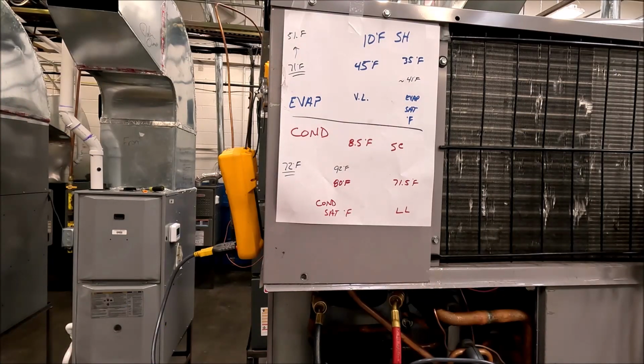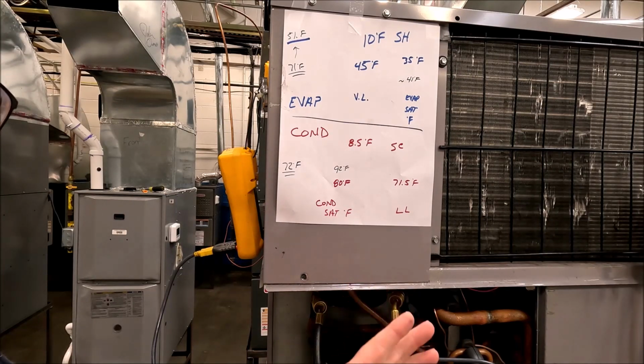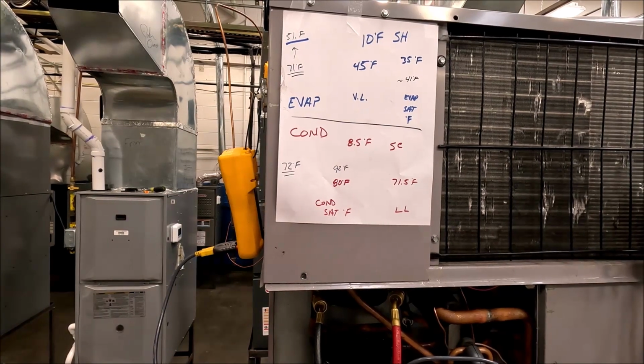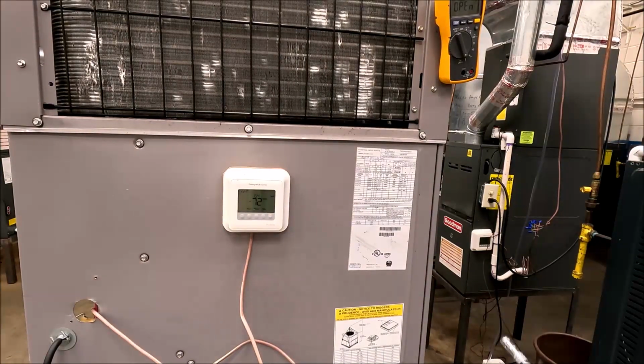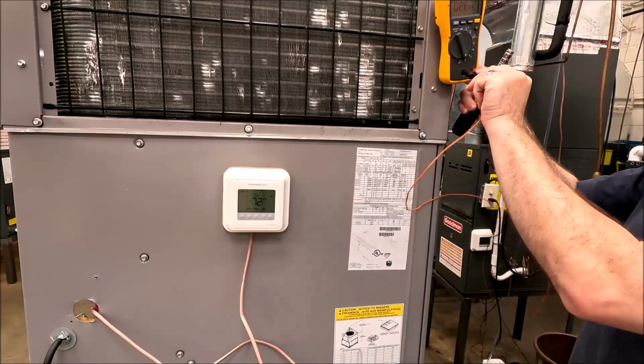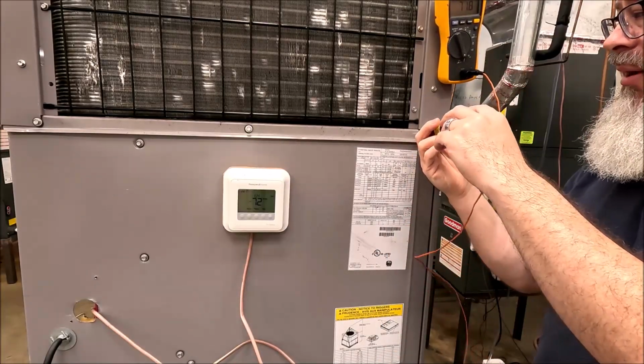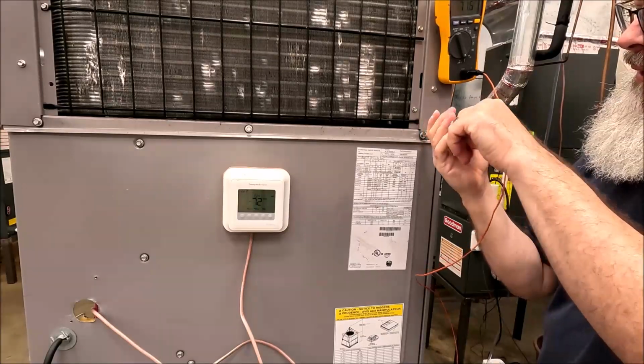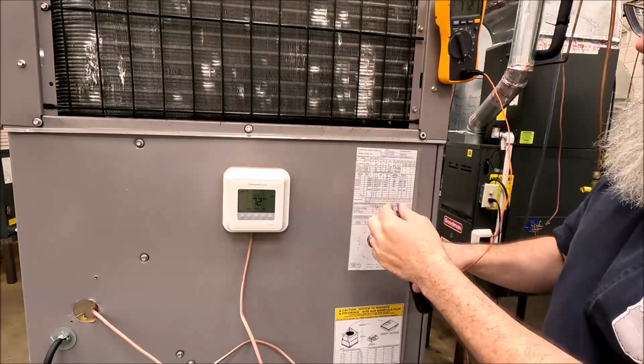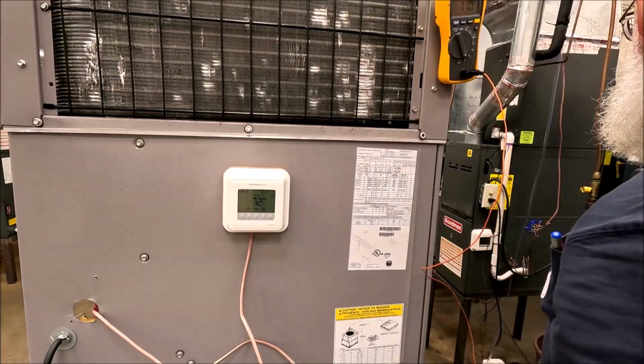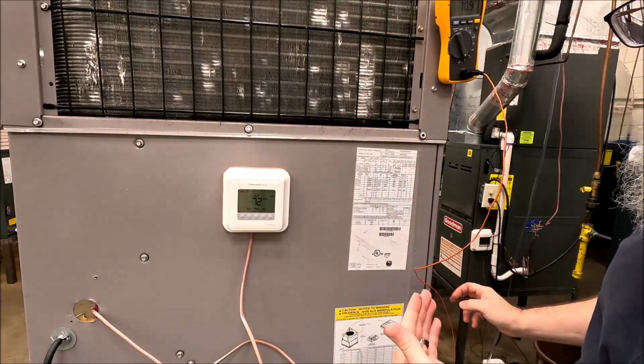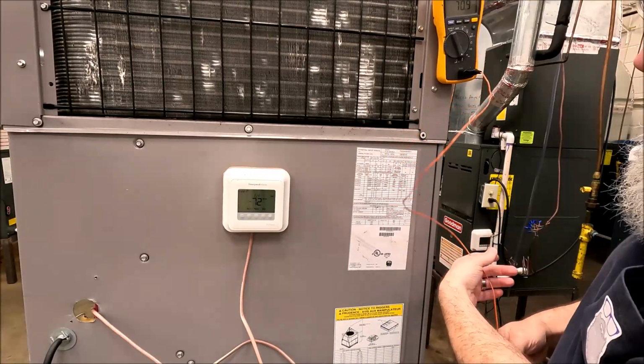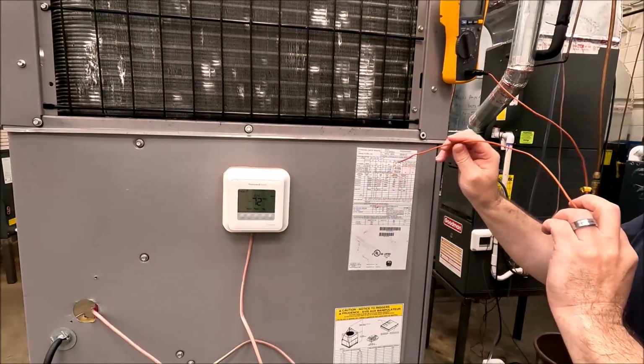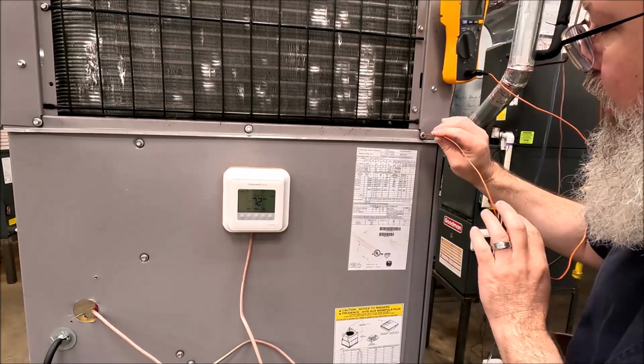So the only other thing that we didn't verify was this air temperature on the supply. So let's walk around to the supply side of this unit and we'll take the air temperature and see what it is. So I'm around on this side. I've got my K-type plugged back into my meter, and I'm going to do the same thing. I'm going to take one screw off, and for me it's usually the one on the top corner, closest to the back of the unit where the ductwork is. And I'm going to take this, and it's got like a slight natural curve to it anyway. I'm going to take and try to see.